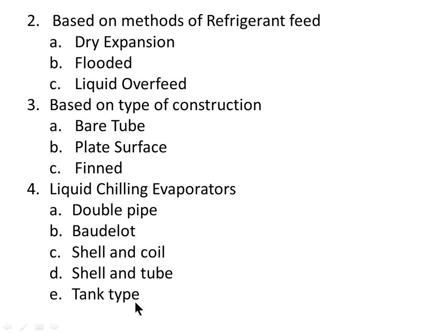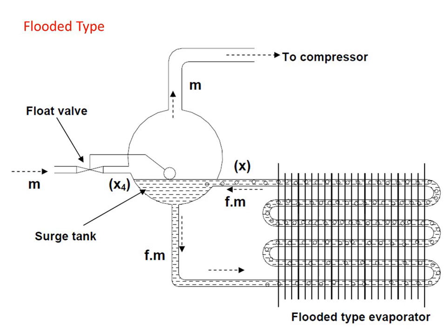First, the flooded type evaporator. In a flooded type evaporator a constant refrigerant liquid level is maintained. A float valve serves as the throttling device maintaining a constant liquid level, keeping the inside surface wetted with liquid — hence it is called a flooded evaporator. Heat transfer efficiency increases because the entire surface of the tubes is in contact with liquid refrigerant, making flooded evaporators more efficient. The evaporator is equipped with an accumulator or surge drum that serves as a liquid reservoir from which liquid refrigerant is circulated by gravity through the evaporator circuit.